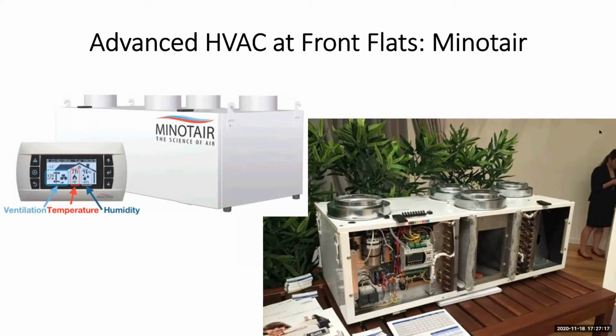Because they have no passive heat recovery, it basically has to be working in heat pump mode all the time, or it doesn't heat or cool at all. They found it uses about 4 times the energy of, say, a Zehnder or a passive heat recovery ventilator. So they're basically saying it's almost impossible to certify to PHI using a Minotair.